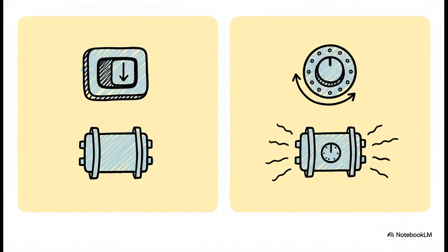There's one other big difference you need to know about: how they're controlled. A fixed reactor is the simple version. It's either on or it's off, absorbing a set amount of power. But a variable shunt reactor, or VSR, is way more advanced. It can fine-tune exactly how much reactive power it's absorbing in real time. That dynamic control is incredibly valuable for the kind of complex, fast-changing grid we have today.